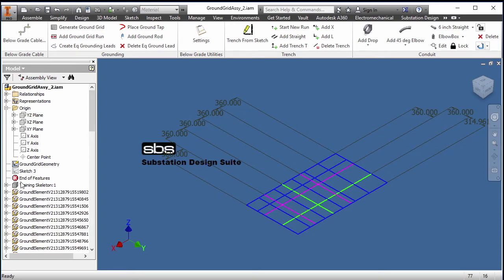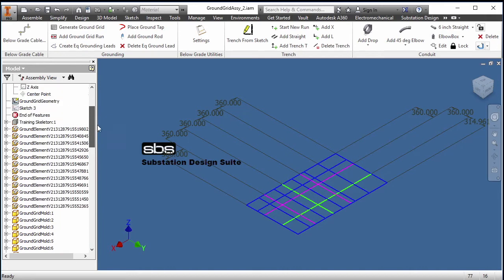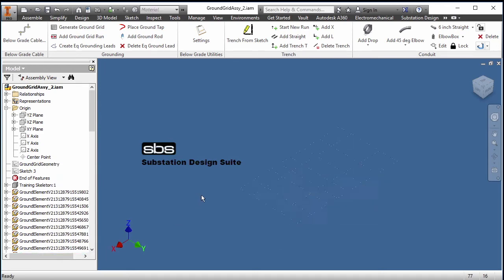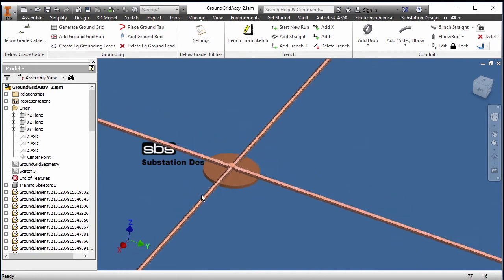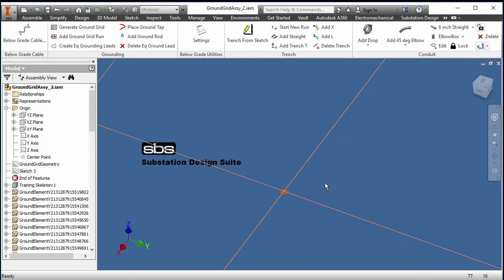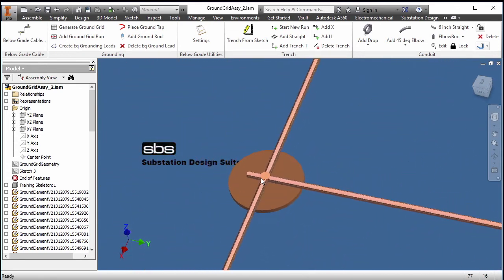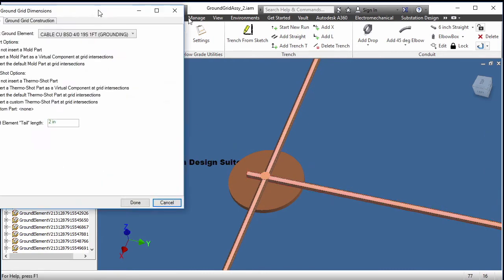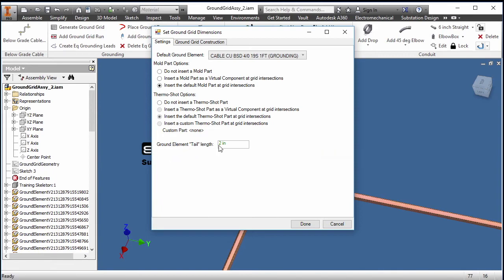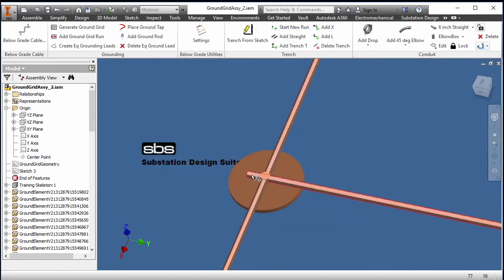In our browser tree, we can see our ground grid elements have been generated and placed. I'm going to turn off the visibility of my sketch since we don't need to see that anymore. We can see a ground grid has been made. Zooming in, we can see we have a mold and shot representation — we have our four-ought cable, a mold, and our shot. Shots are consumable, but we show them so we can count all our shots. At the endpoints where it overlaps, you can see the two-inch overlap, which corresponds to the ground grid tail length of two inches set in the generate ground grid tool.